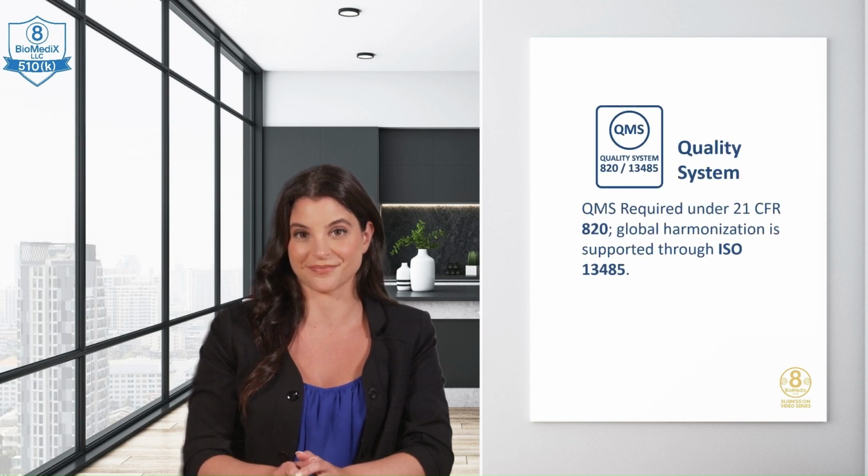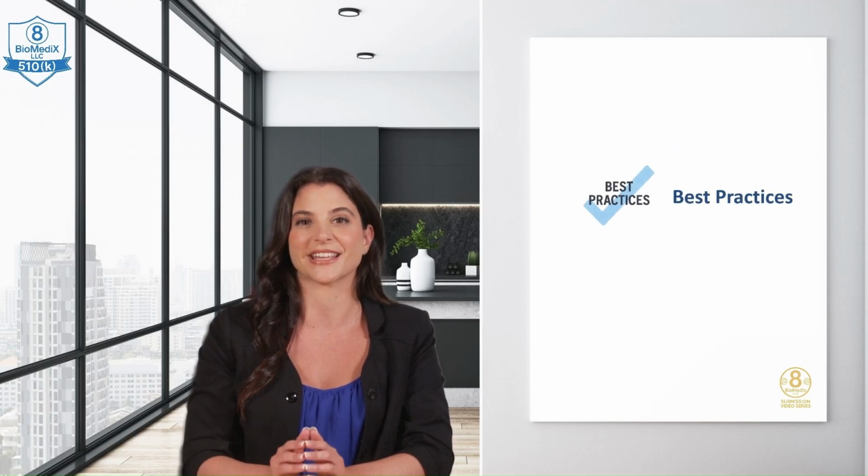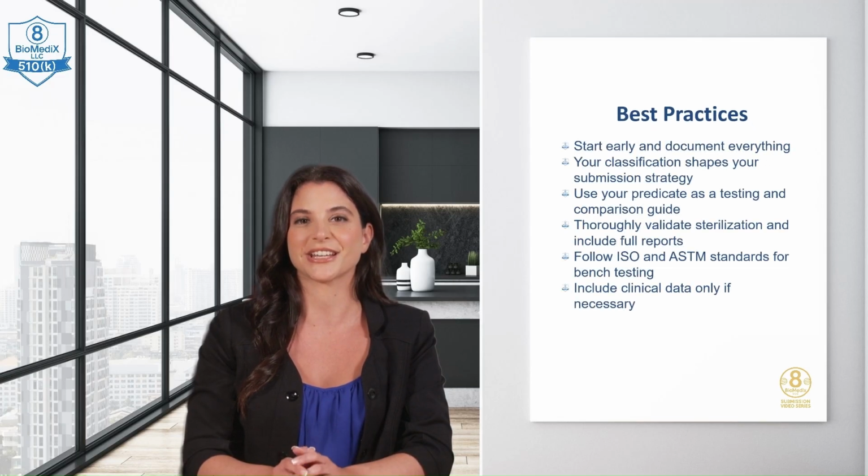Best practices. Start early and document everything. Your classification shapes the entire submission strategy. Use your predicate as a guide for testing and comparisons. Validate sterilization thoroughly and include full reports. Follow ISO and ASTM standards for bench testing. Only include clinical data if necessary, and plan early, especially if using a pre-sub with the new eSTAR template.